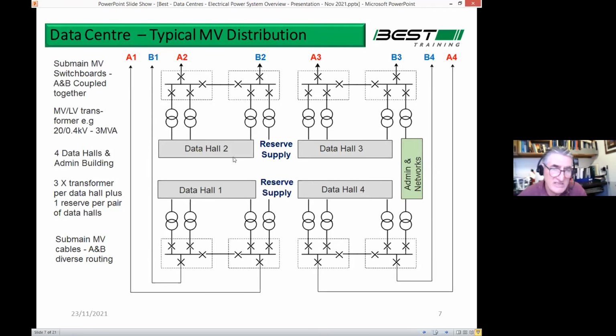Each of the data halls has 3 transformers, so they're really a mirror image of one another. And then you see there's a reserve supply in the middle. The reserve supply is like your +1, your spare system. That spare system can take the place of any of the other transformers to the left or the right. So if one of the transformers has to come out of service, this reserve supply can be switched in. I haven't shown on the schematic how it's switched in. We look at that later. It'd be too complex to show on this diagram.